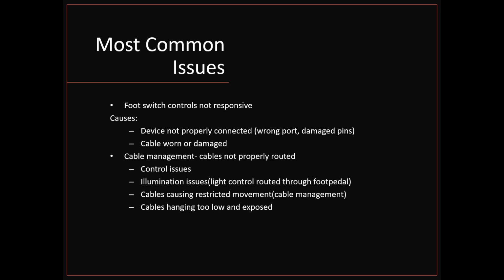Cable management is an issue as far as controlling the microscope. A cable that's pinched or hung up somewhere can cause the electromagnetic clutches not to work correctly. Or if it's a manually balanced or manually braked scope, if the cable isn't routed properly, surgeons will spin it and keep spinning because they can't get it to go far enough, and then you get broken fiber optic cables and broken wires.